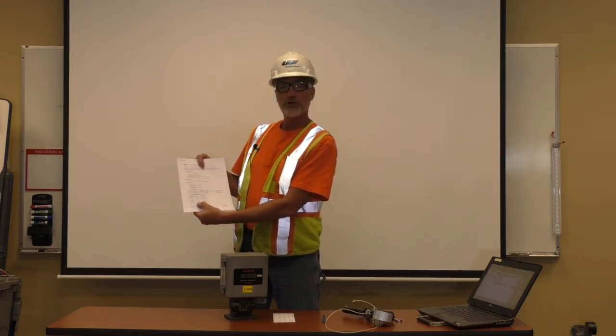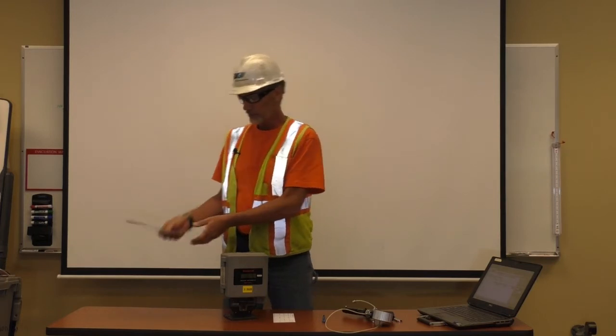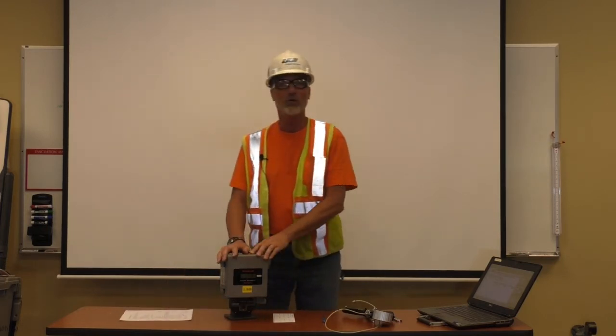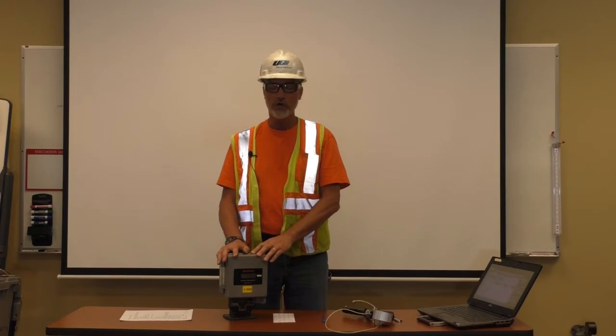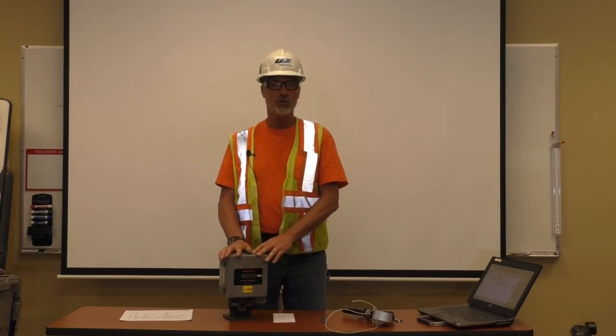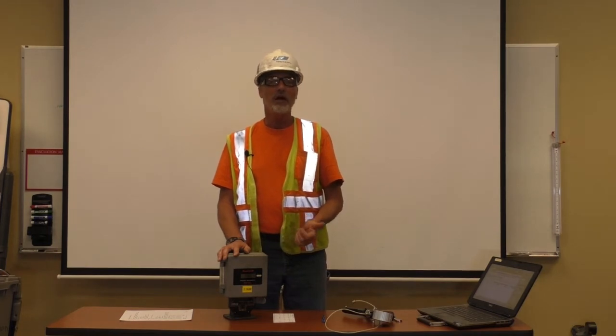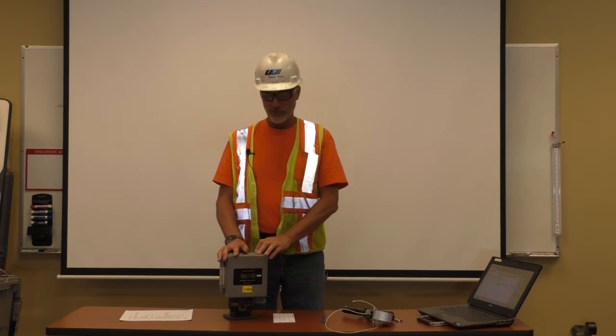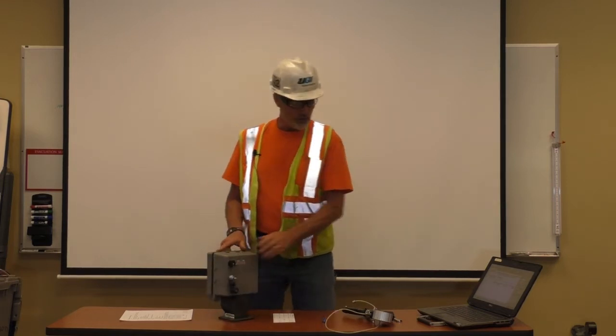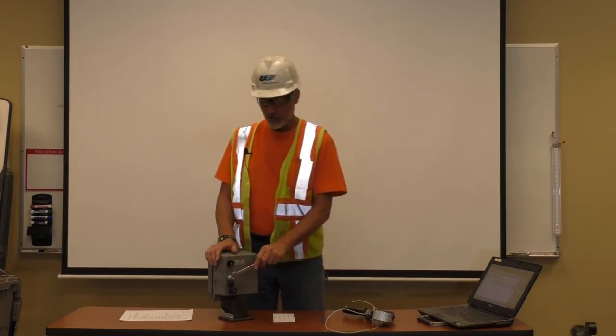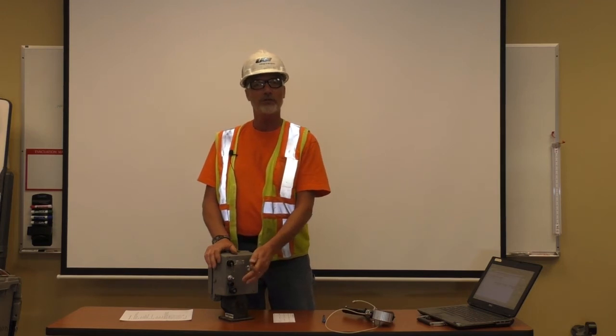On your meter correcting test procedure, there's a list at the bottom for which transducer you're dealing with, and it tells you which pressures that you can be between. So on the low side, on this P only 0 to 100, our low test is 20 pounds. So as long as it's anywhere between 15 and 25, you're good to do your test.